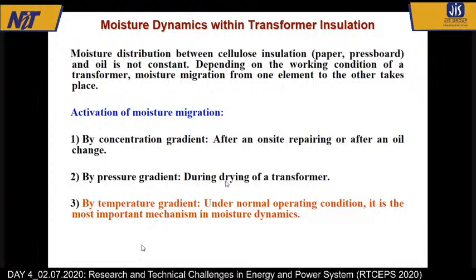But what happens every day is called the temperature gradient. As the temperature goes up and down, it has now been conclusively established that moisture moves between paper and oil. When the temperature increases, moisture moves from paper to oil. When the temperature decreases, moisture moves from oil to paper. The interesting part is that the time constants of these movements are different: moisture moves from paper to oil at a faster rate, but from oil to paper at a slower rate. Now this has an important bearing.